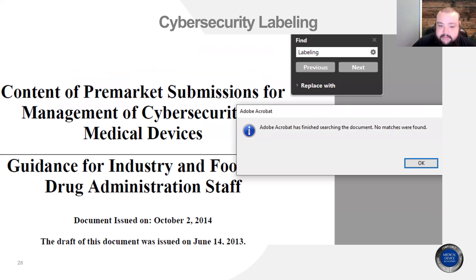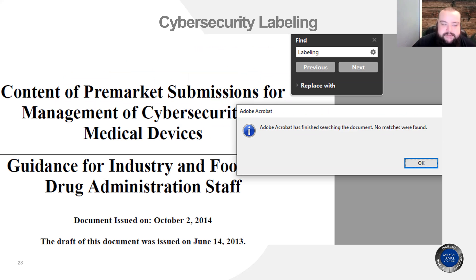Unfortunately, if you look at the PDF revision, labeling isn't even mentioned in the guidance document, and that's what makes cybersecurity labeling such an interesting topic right now. It's kind of in between suggestions and guidance for how to be compliant with what the FDA is looking for in pre-market submissions.